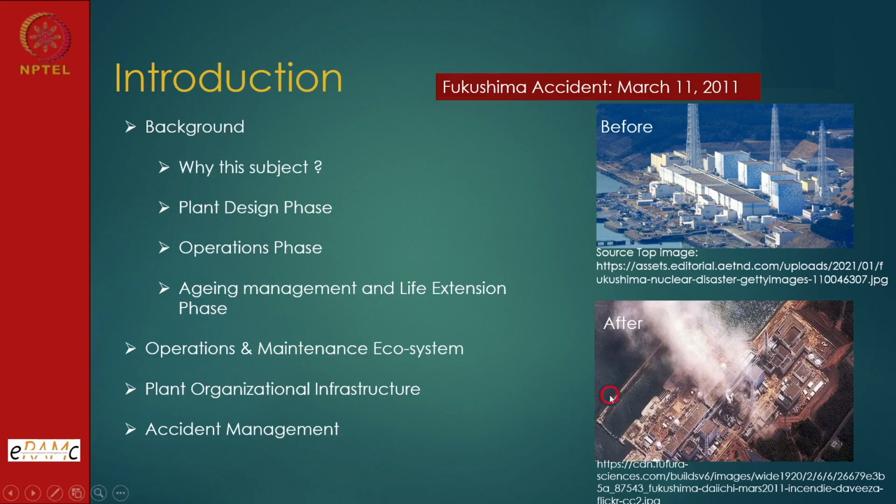And this is a no-no situation. This is Fukushima 2011, the earthquake in the water body, which then manifested into a tsunami. As I mentioned, there were safety provisions. There were 7-meter walls around the plant, but the wave height was a little higher, and there were some safety recommendations which were to be met. And then the power failure, station blackout condition, and finally it took its toll in terms of hydrogen buildup in the reactor cavity, and then finally the explosion, and it had very long consequences.